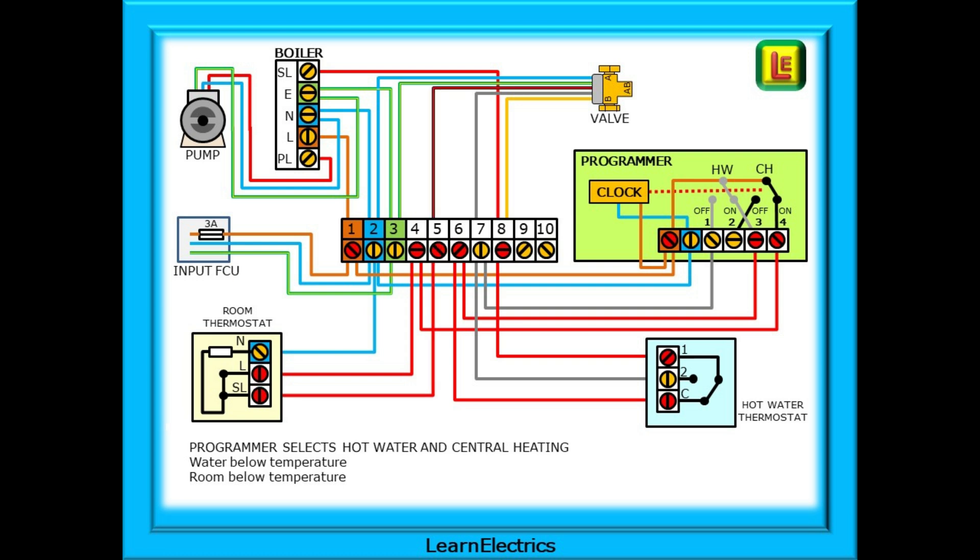Later the room thermostat changes position and connects L to SL. The 240 volts at L passes to SL and back up to the wiring center terminal number five and along the white wire to cause the valve to allow heating water to flow through the output port A as well as B. Wiring center terminal eight is already holding the boiler and pump in the on position.